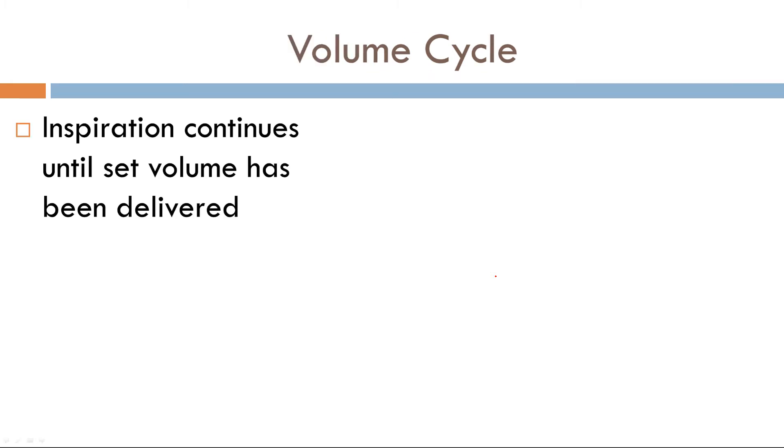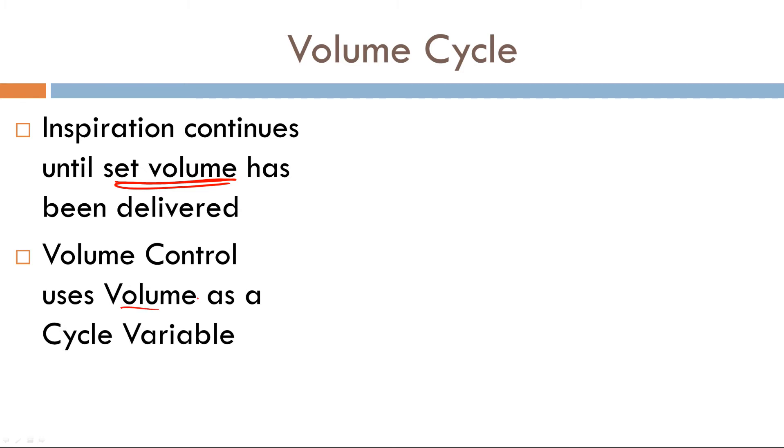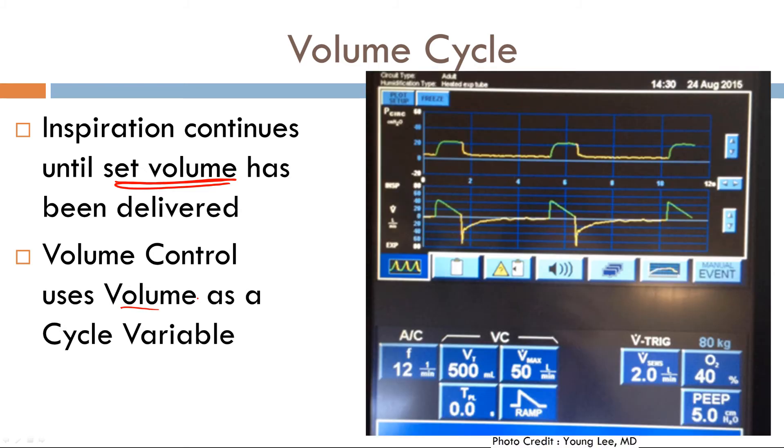Let's talk about volume cycle. The definition again is inspiration will continue until a set volume has been delivered. So interestingly enough, in volume control ventilation, the cycle variable is volume. So let's take a look here. We have pressure. We have flow here. As you can see, the cycle variable has been set to 500 milliliters. So once 500 cc has been delivered, boom, stops delivering your breath.